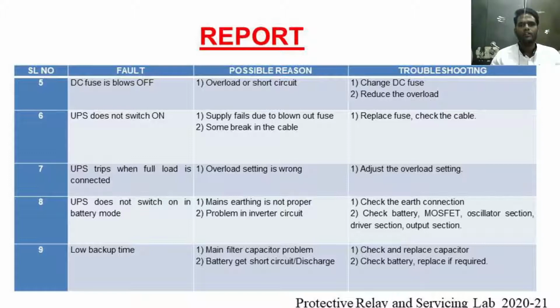So the last one is low backup time. This is mainly because of a problem with the main filter capacitor, or the battery getting short circuited or discharged. For this, the solution may be to check and replace the capacitor, and check the battery and replace it if required.